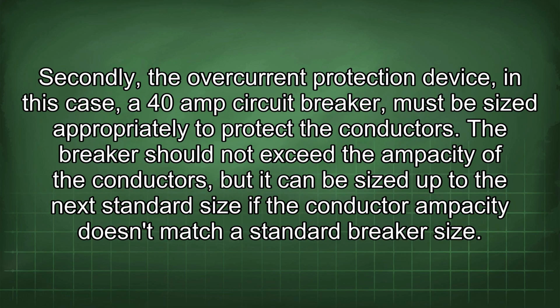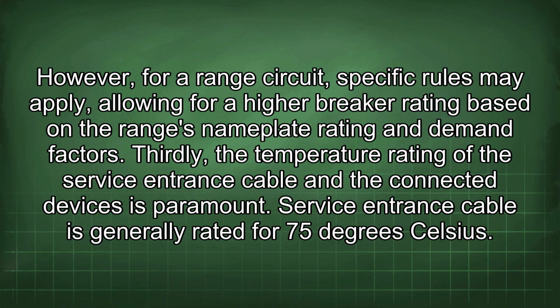Secondly, the overcurrent protection device, in this case a 40 amp circuit breaker, must be sized appropriately to protect the conductors. The breaker should not exceed the ampacity of the conductors, but it can be sized up to the next standard size if the conductor ampacity doesn't match a standard breaker size. However, for a range circuit, specific rules may apply, allowing for a higher breaker rating based on the range's nameplate rating and demand factors. Thirdly, the temperature rating of the service entrance cable and the connected devices is paramount.